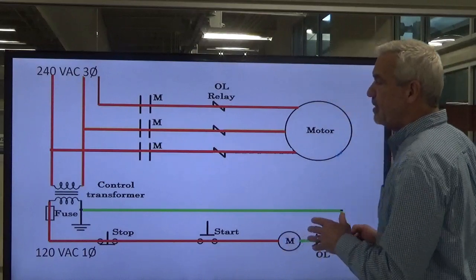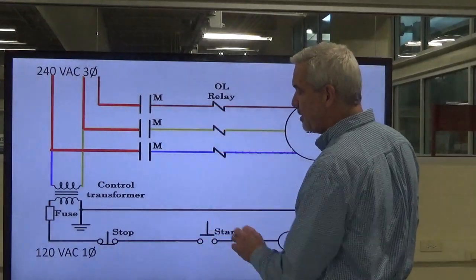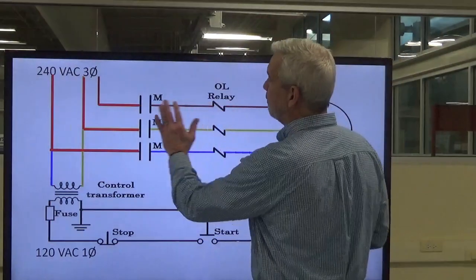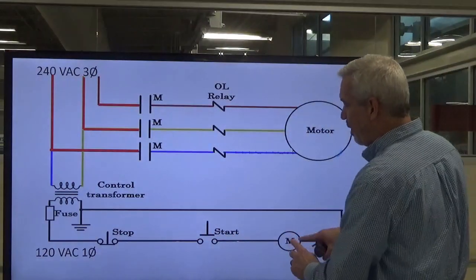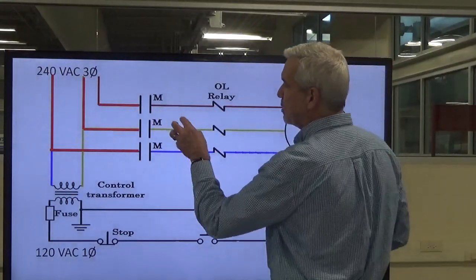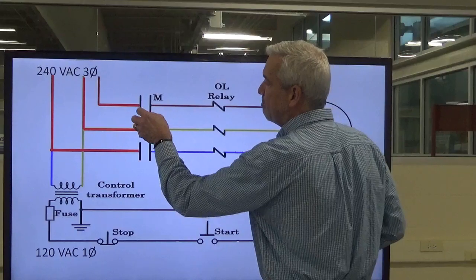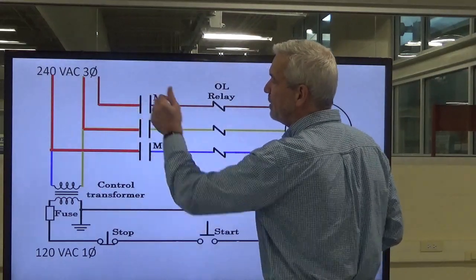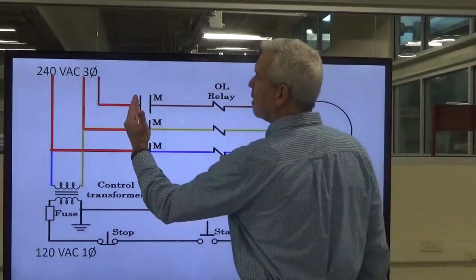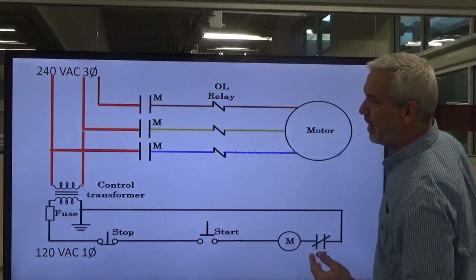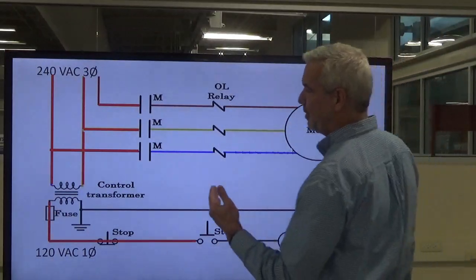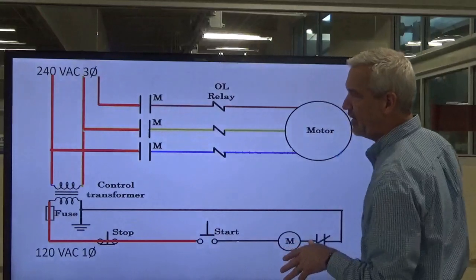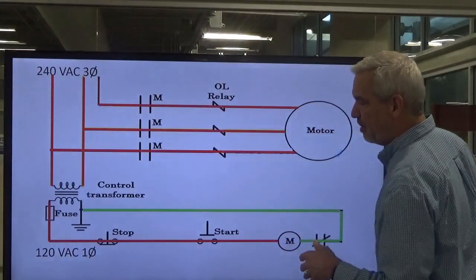Okay, so the second that I take my finger off the start button, then we lose the voltage to our coil. Our coil de-energizes, and a spring overtakes and pops these normally open contacts open, and here sits our voltage parked again. Now, the one thing I don't have is, there you go, that's what really should happen. That should be where that's at right now. So I'll just kind of run back through that real quick.